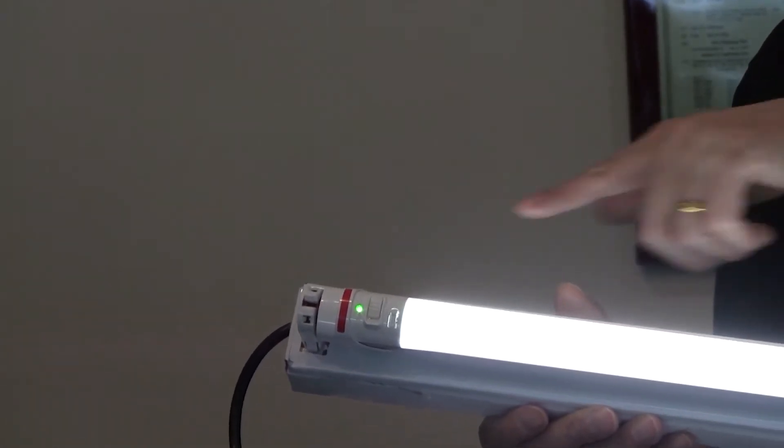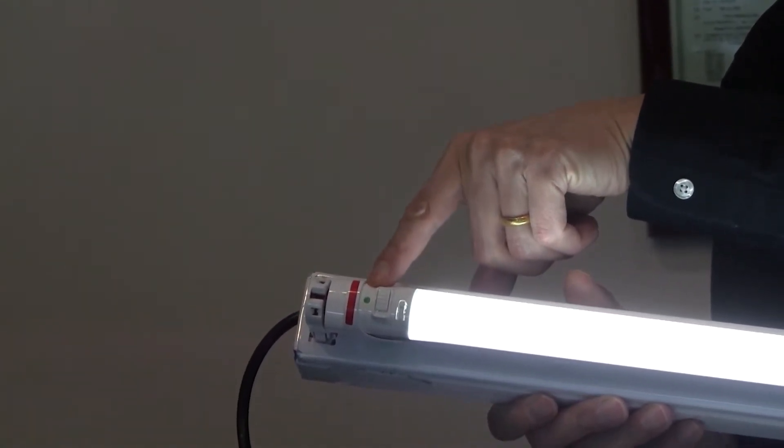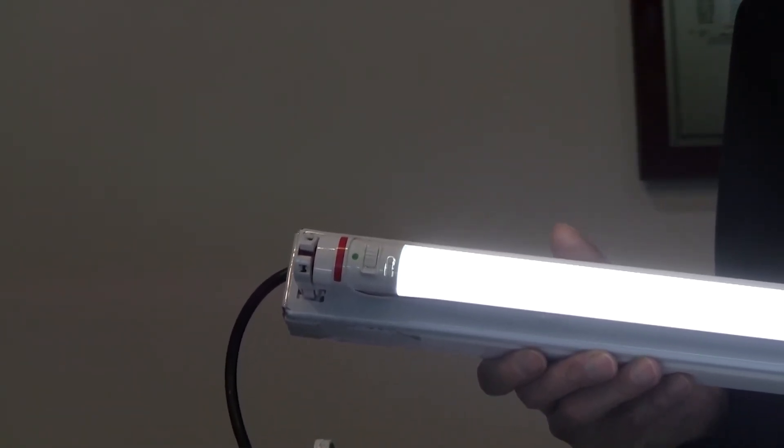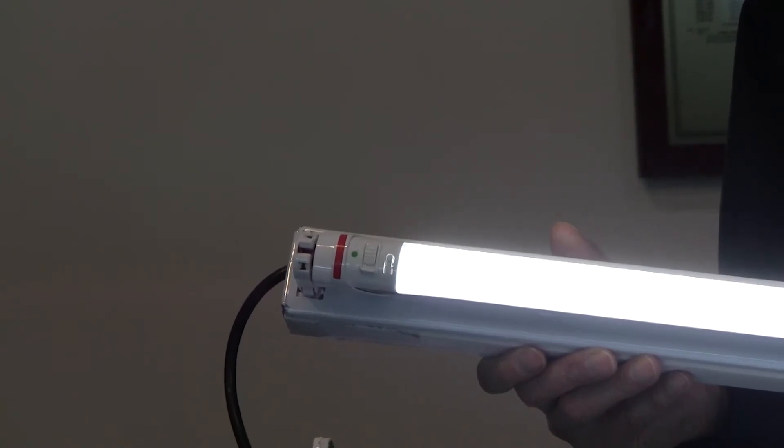With the self-testing self-diagnosis feature, the lamp will automatically run the 30-second monthly and 90-minute annual test. This meets the emergency lighting audit requirements with no labor cost to the user.